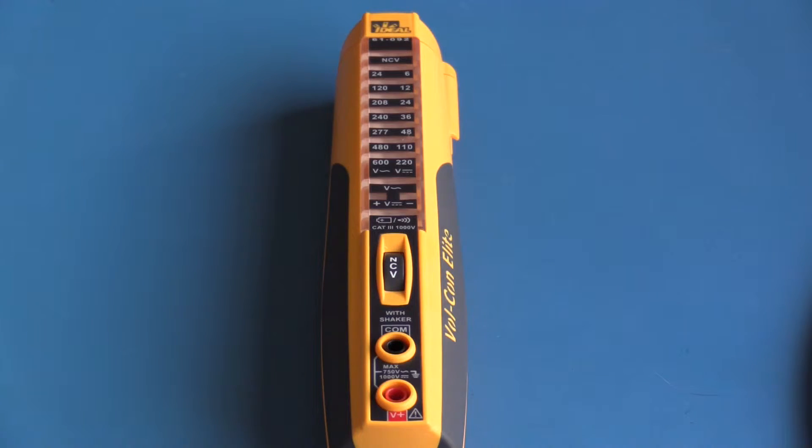However, in my review of non-contact voltage testers, I mentioned that a non-contact voltage test is a good tool to determine that voltage is present, but it should not be used in an application where you are determining that voltage is not present. I'm going to demonstrate why.